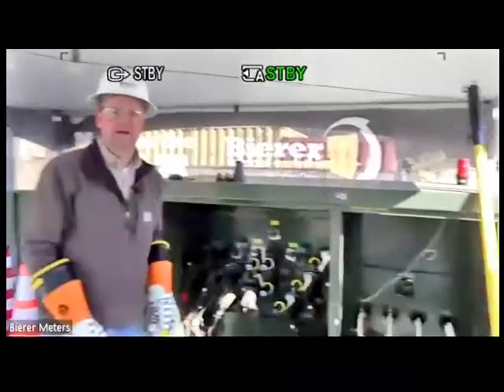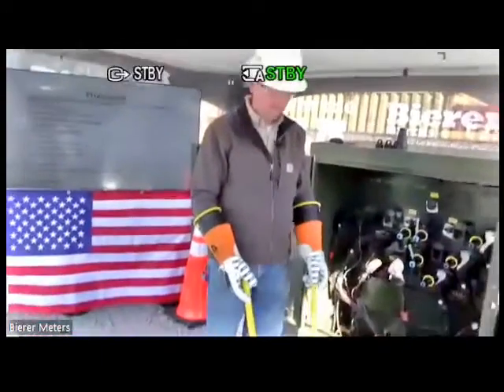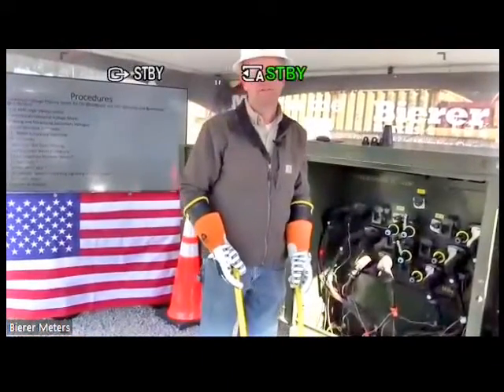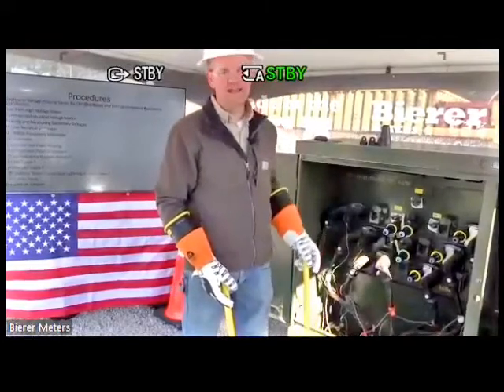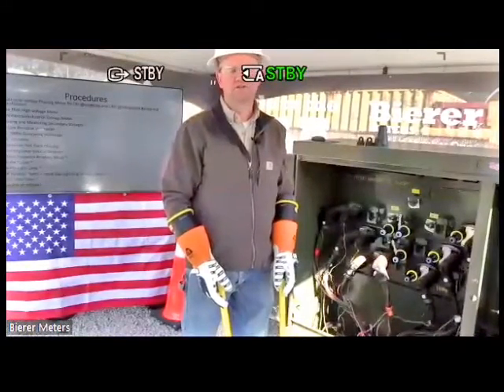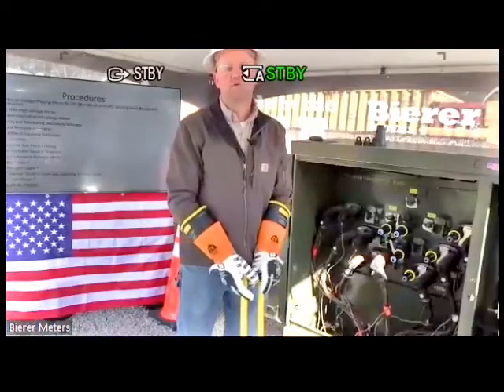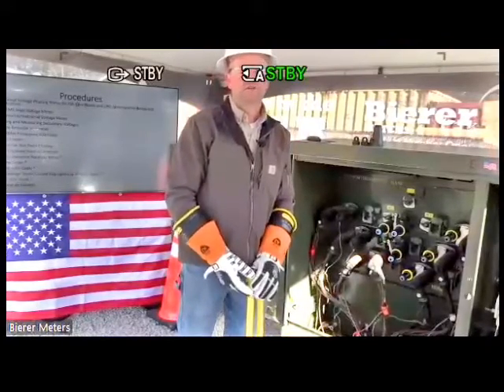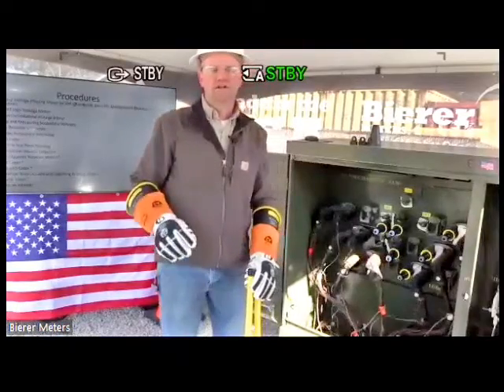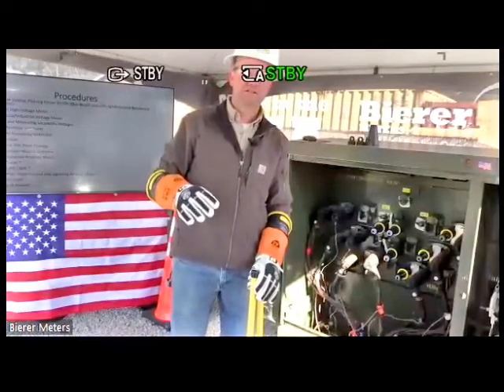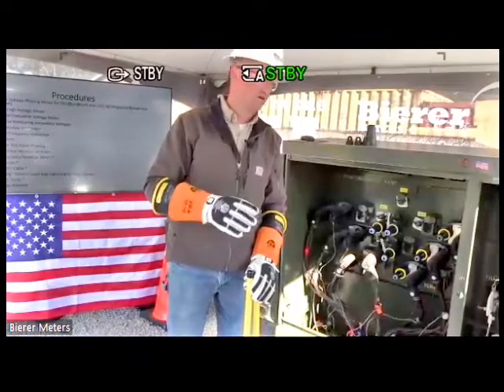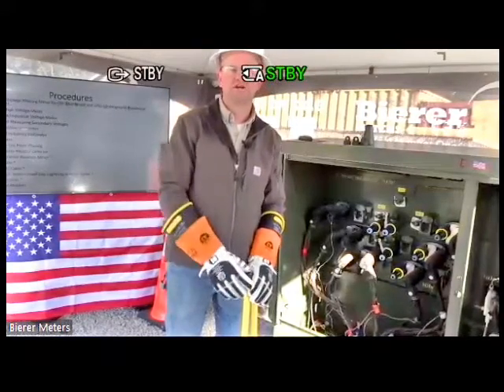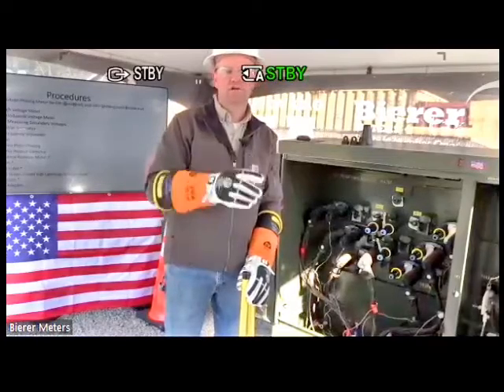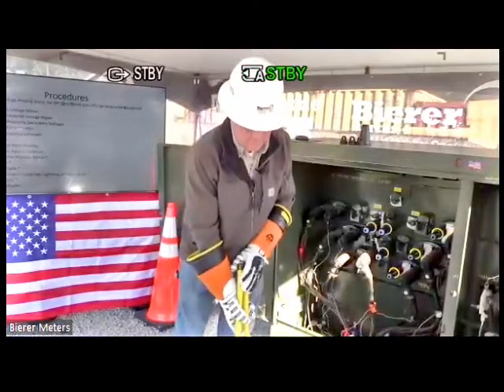So again, capacitive test point phasing. Verify that your capacitive test points are good, phase to ground, and then go about phasing. Obviously we have our phases taped here, so we're cheating a little bit. We know what's in phase and out of phase, but your reading will actually tell you. So your in phase number should be lower than your phase to ground and phase to phase readings. That number should always be lower. You saw your 300-ish, roughly around 300. That number was consistently lower on all 3 phases in phase. Okay, that's your capacitive test point phasing.